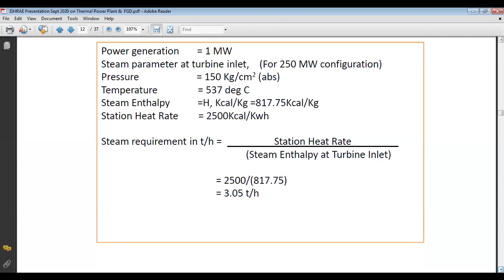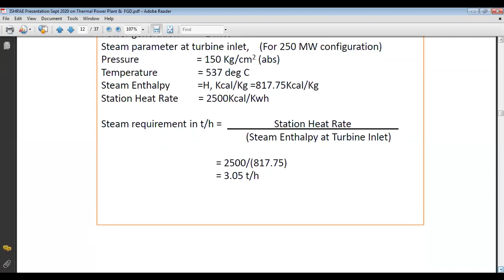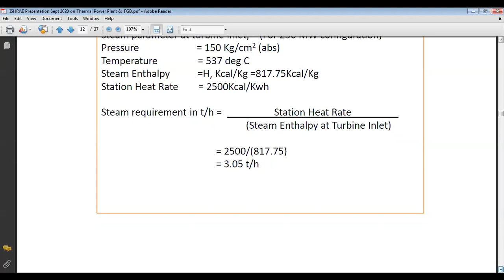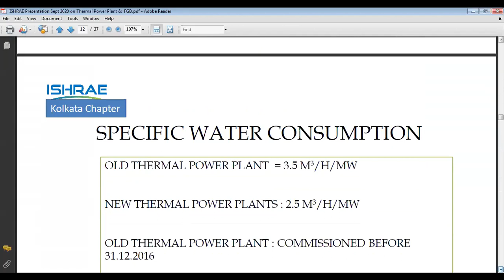817.75. So using this formula, you can calculate how much steam is required to generate 1 megawatt. So it is coming around 3.05. So this steam requirement per megawatt depends on the station heat rate of the power station, as well as the operating parameters like pressure and temperature. So if you know the operating pressure and temperature, the steam enthalpy can be taken from the steam table and the station heat rate, then you can calculate very easily the steam requirement per megawatt. This is another thing.